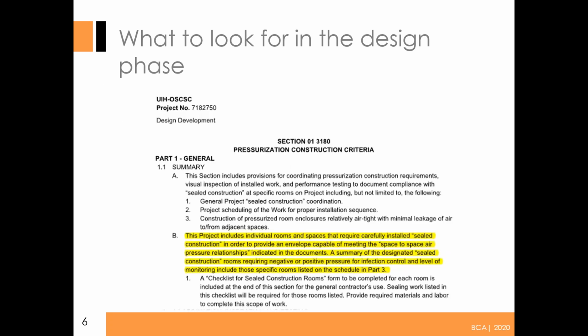One thing I've seen recently is a spec on one of my jobs, and I have it highlighted in yellow, but essentially they have a spec called pressurization construction criteria. They're actually telling the contractors how they want the room to be built. And that sounds like a no-brainer, like why don't they always do it? But they have it. This is something that I'm seeing new for the first time. And it's recognized that if you don't have the room tight, you can't have the exhaust system, or you can't have the supply system big enough to overcome it. And we'll get into that example.